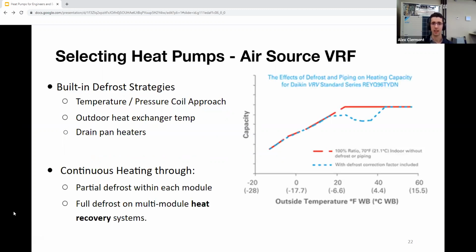Now we're staying on the topic of air source heat pumps, and we're going to talk about defrost, which I quickly introduced in the cold climate slide. The chart here on the right shows the heating capacity of a VRF unit based on outdoor temperatures, moving from right to left again. You have the temperature going down and the capacity up and down. So right around as you get to 25 degrees Fahrenheit, you see that capacity starts to go down based on ambient temperature.